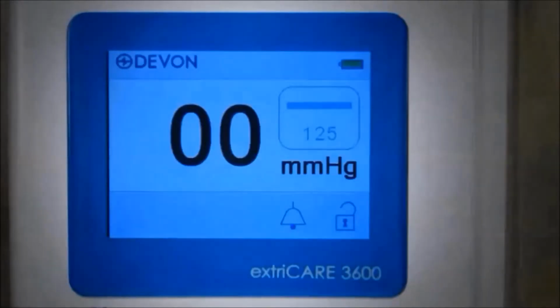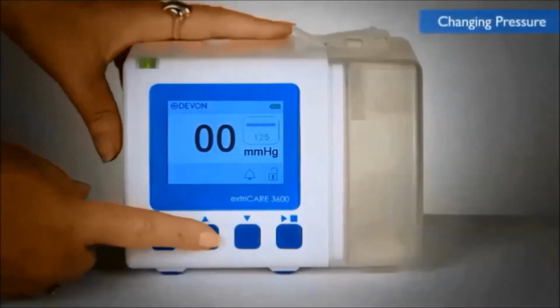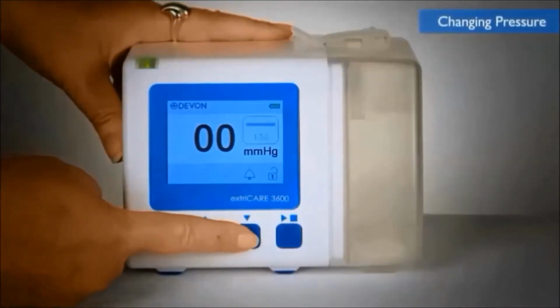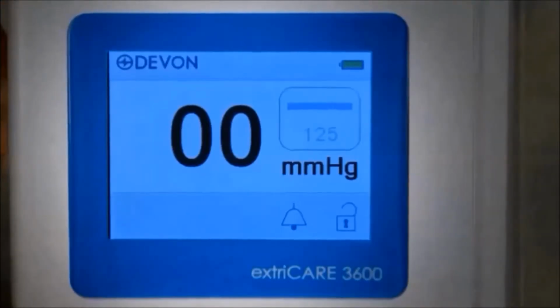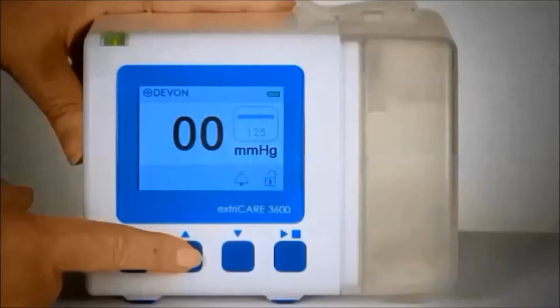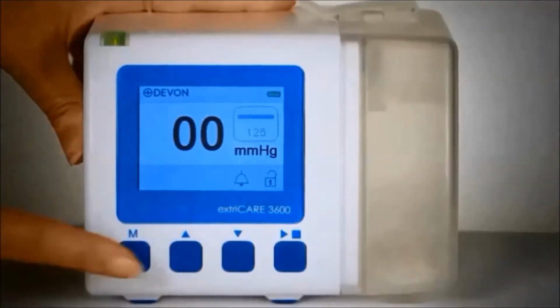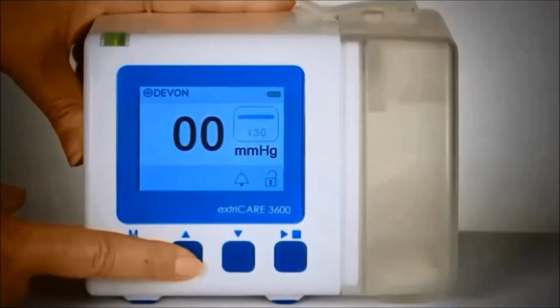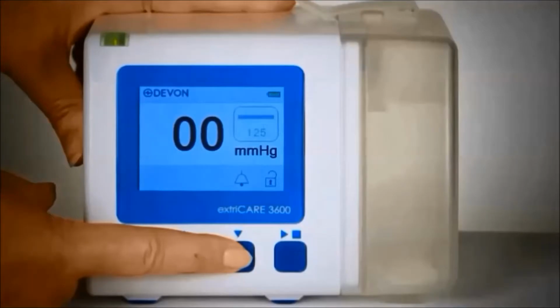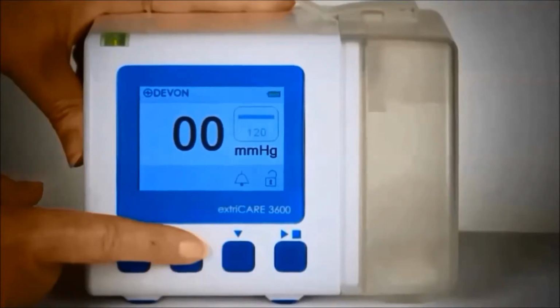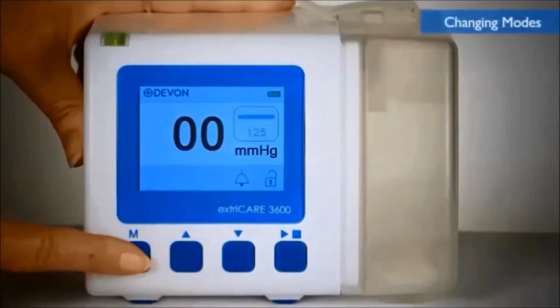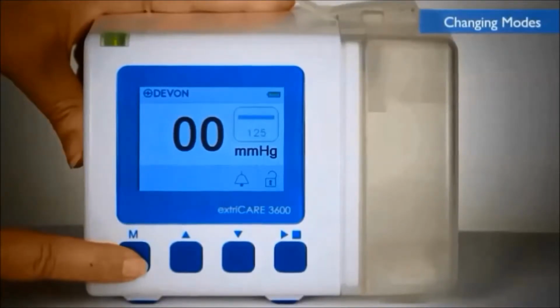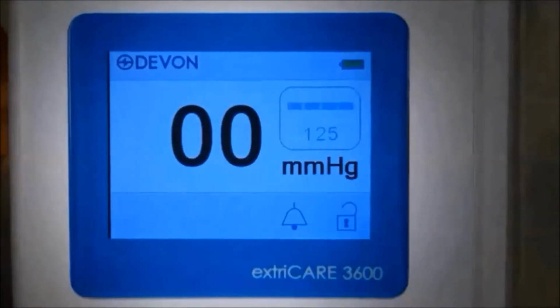The extriCARE 3600 has a default pressure of 125 millimeters of mercury. To change the pressure, press the up or down buttons. The pressure will change in increments of 5 millimeters of mercury with a range of 40 millimeters of mercury to 200 millimeters of mercury. By holding down the up or down button, the pressure will change continuously in 5 millimeters of mercury increments. To change the operating mode, press and hold the mode button until the mode icon changes.